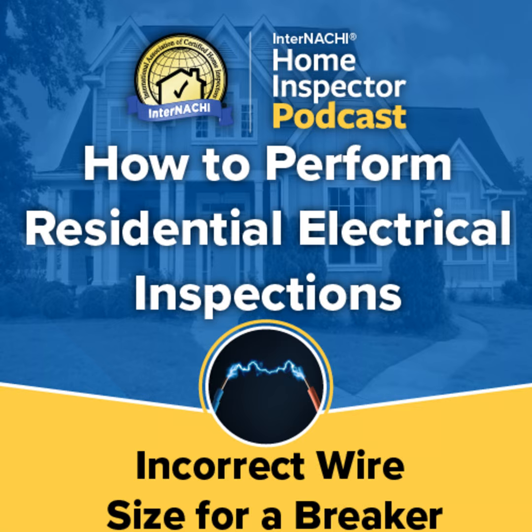Incorrect wire size for a breaker. An incorrect wire size or gauge is a common observation by a home inspector when inspecting 15 and 20 amp breakers at the electrical panel board. An incorrect wire gauge may be found at any breaker. An example of an incorrect wire gauge is where a 14 gauge wire is connected to a 20 amp breaker.